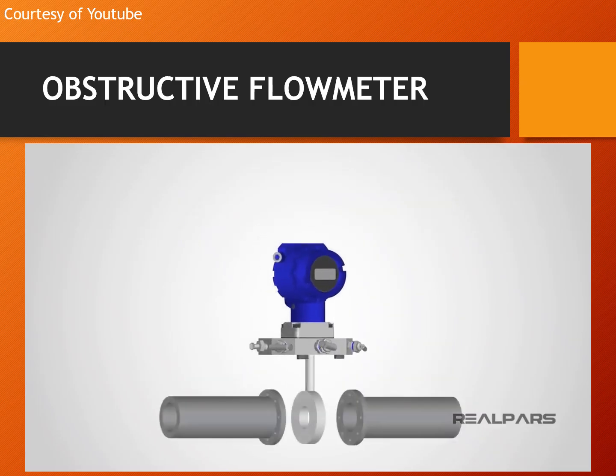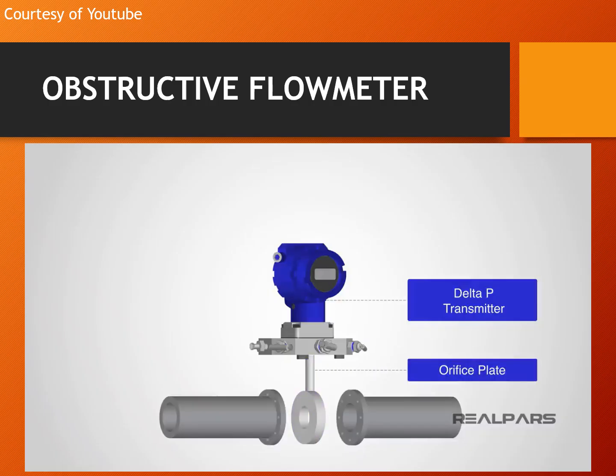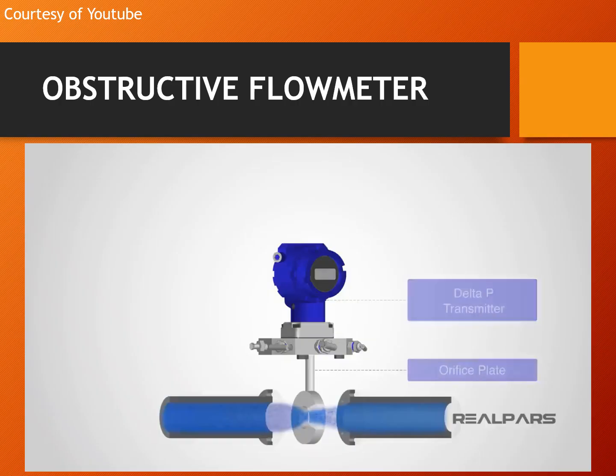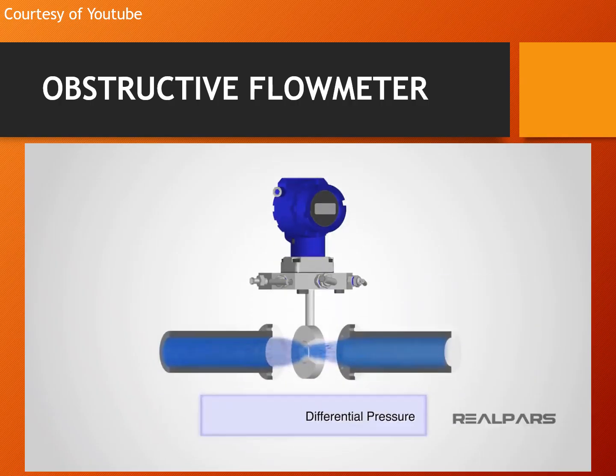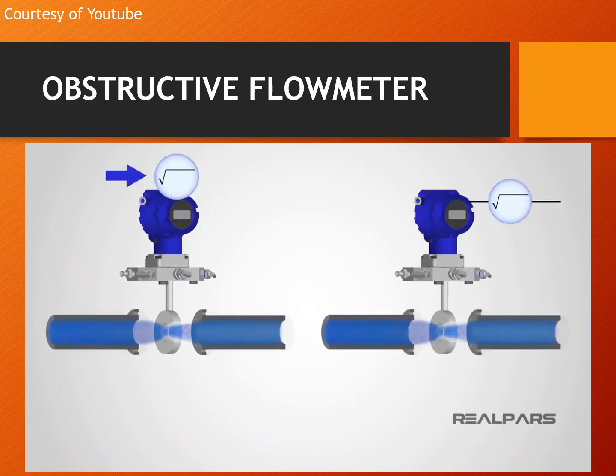A common method of flow measurement is done by using a differential pressure transmitter. The differential pressure transmitter, often referred to as a delta P transmitter, is placed across an obstruction such as an orifice plate. The orifice plate will cause a varying differential pressure drop across it as the flow through the pipe changes. Unfortunately, the differential pressure across the orifice is not proportional to the flow rate, but is actually proportional to the square of the flow rate. That's why in applications like this, we need a square root extractor. Sometimes this square root function is built into the transmitter, and sometimes a square root extractor is a separate signal conditioning instrument connected to the output of the transmitter.